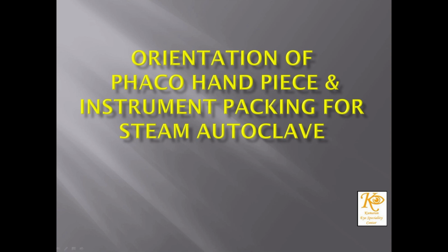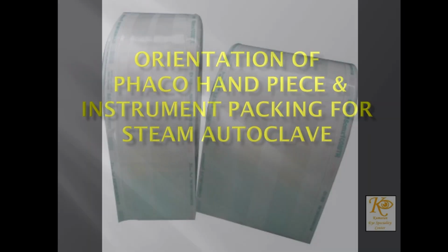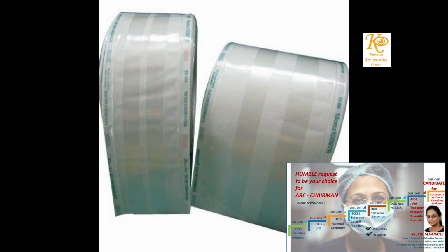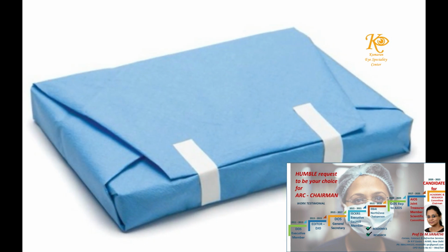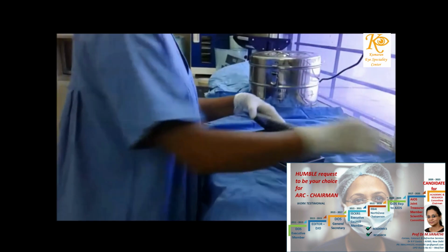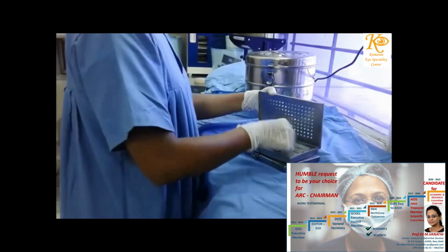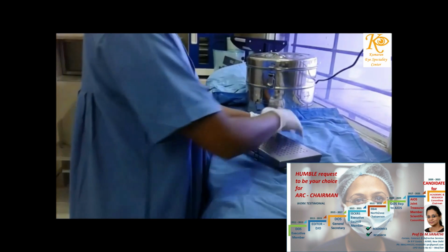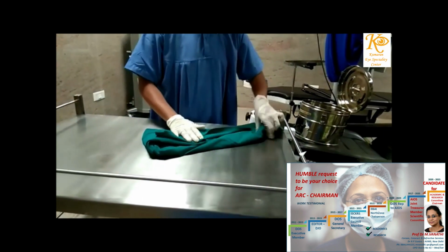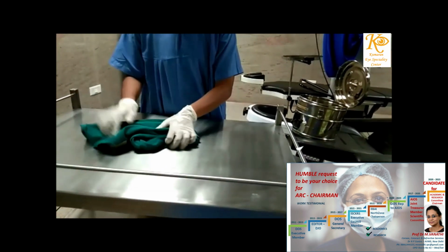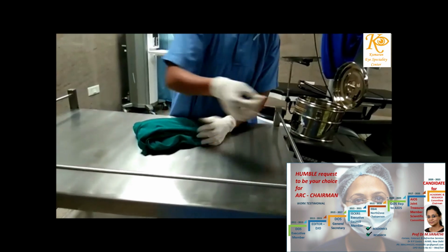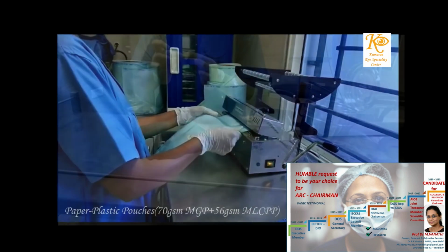Packing and orientation of hollow surgical instruments in the autoclave is important for the success of sterilization. Here we discuss the packing materials and the orientation of the phaco handpiece in the sterilizer. Packing can be done with three different types of materials, namely lint-free woven linen or non-woven paper. One can use the envelope technique of wrapping for smaller loads or the box technique of wrapping for larger loads.